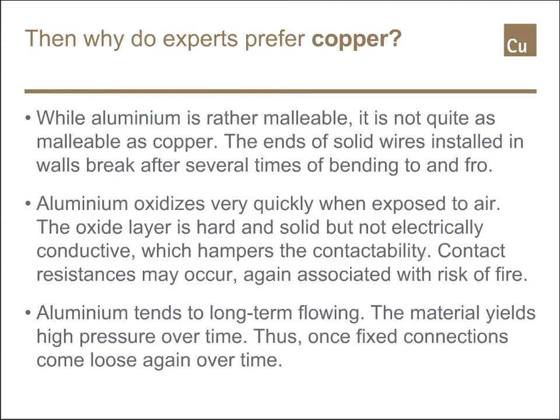And the third point is that aluminium tends to long-term flowing. That means the material is fairly soft, and under high pressure, it tends to yield, and contacts once fixed become loose over time and have to be re-screwed once a year or so, and that is not practical. Now, under the present price situation on the copper market, of course, we observe some substitution of copper with aluminium, but sometimes it also goes the other way around.